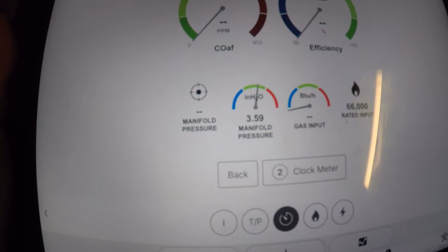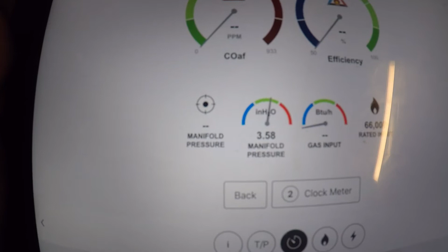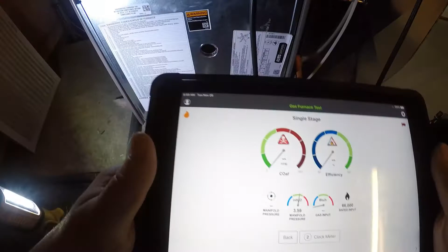So I'm going to do a dial test, see where my input's at, then come back in, adjust my gas pressure, and then adjust everything else. Setting the input is by far one of the most important things you could do. Get your input right, get your temperatures right, temperature rise right, and long term, everything else should be fine. And then what we'll do is we'll come in and do a combustion test to make sure everything else is doing good. A little tip I do.